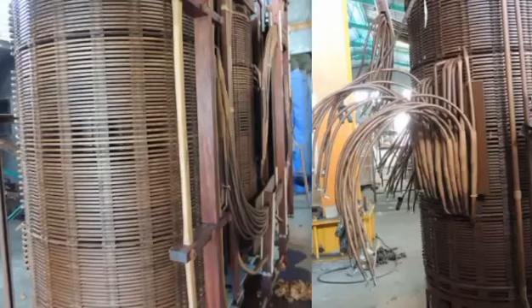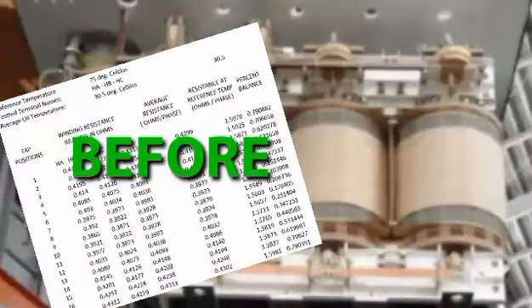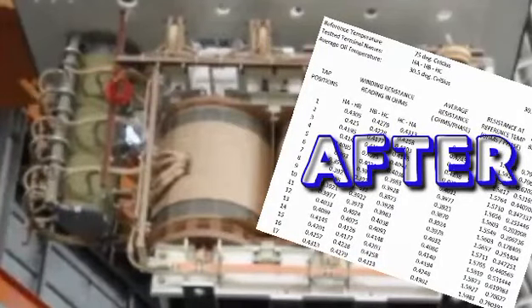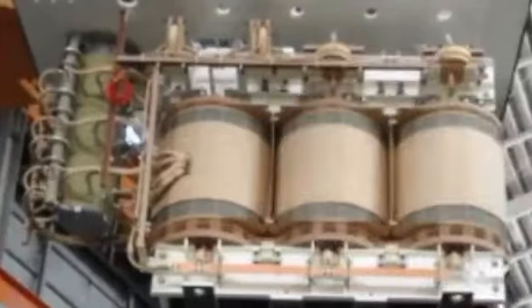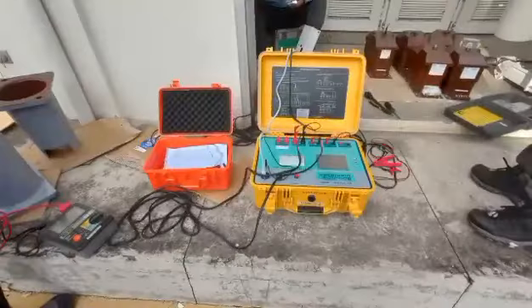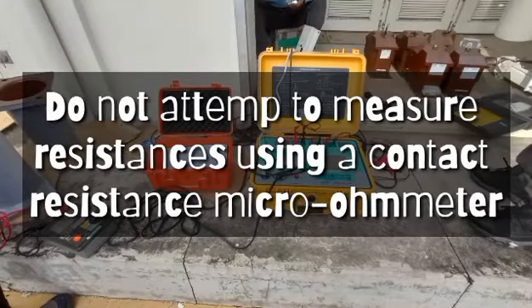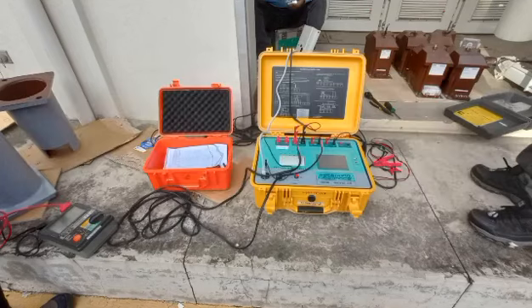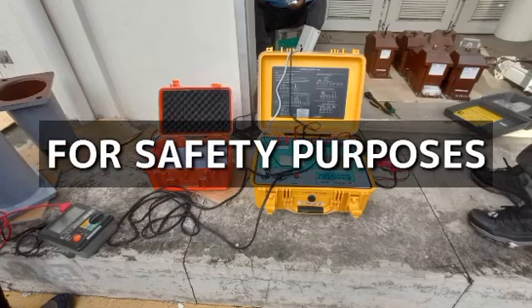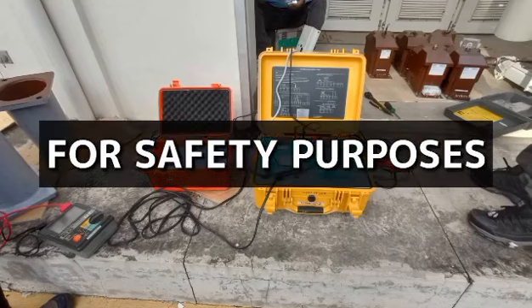Measure the resistance of each winding at the rated and extreme tap positions and compare the results to the original value in the factory test report. If the tap changer connections have been made at site, measure resistance at all positions. Do not attempt to measure resistances using a contact resistance microohmmeter. A safety hazard for operating personnel occurs when the inductive charge created by the windings arcs across to the leads as they are withdrawn from the windings.